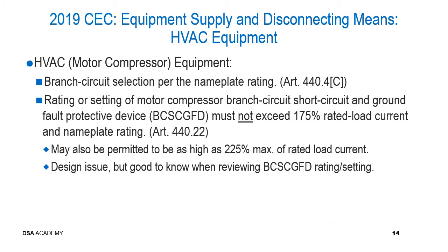Now we're going to talk specifically about the disconnecting means for HVAC equipment, heating, ventilation, and air conditioning equipment, specifically motor compressors associated with HVAC equipment. Branch circuit selection is required to be in compliance with the nameplate rating, and this is identified in Article 440.4(C).